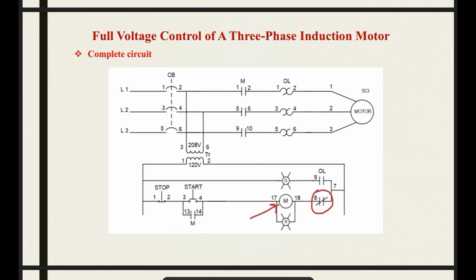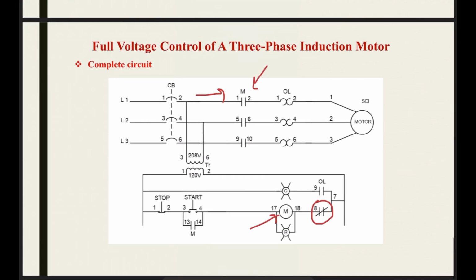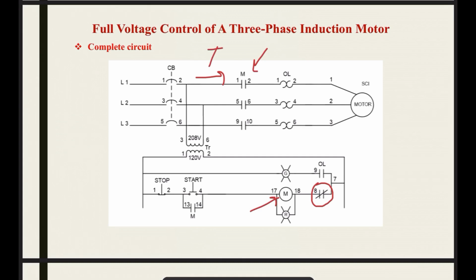The M coil, the main coil, will de-energize. The M normally open contacts in the power circuit open. It was closed, but now it will open. Power is off from the motor now, because M is open, so no current will flow. Now the OL overload normally open contact will close. A green lamp is now on to indicate that the motor has been stopped under an overloading problem.